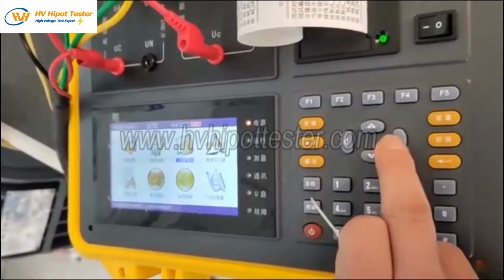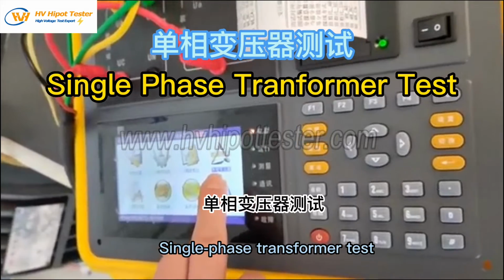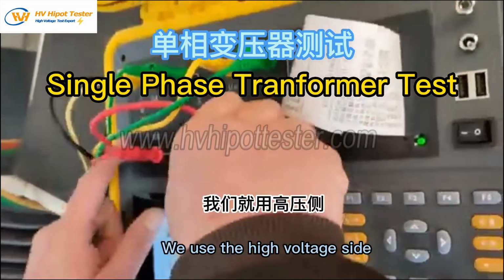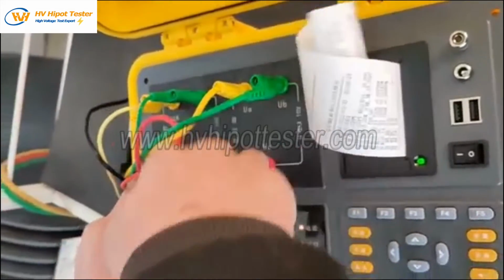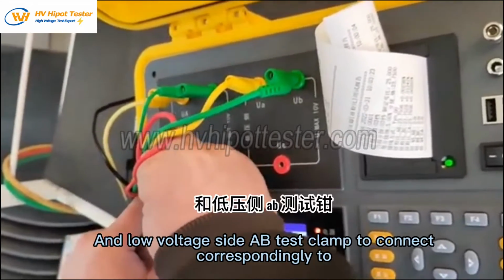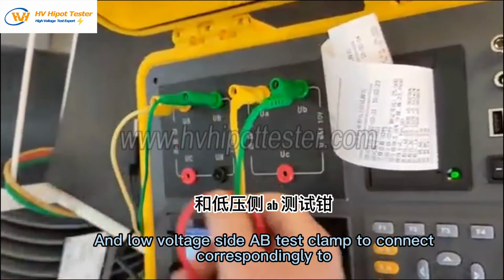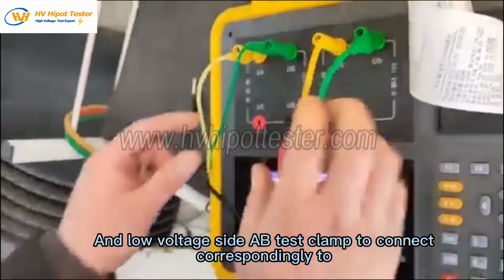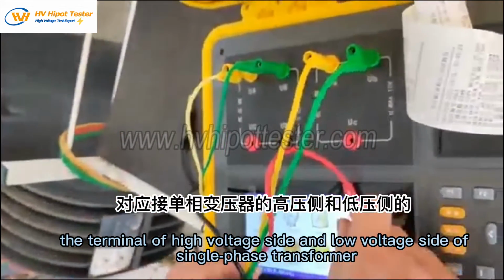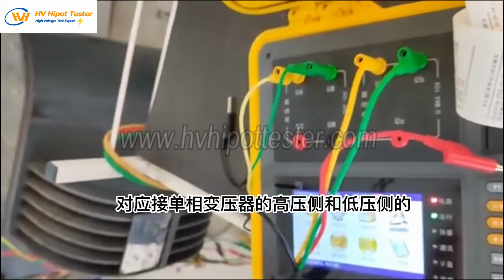Then, single-phase transformer test. We use the high voltage side AB test clamp and low voltage side AB test clamp to connect correspondingly to the terminal of high voltage side and low voltage side of the single-phase transformer.